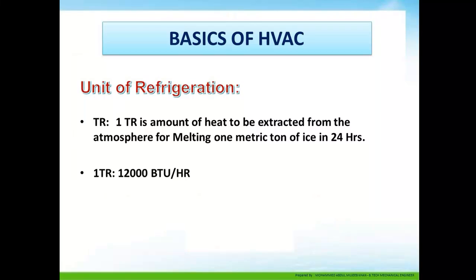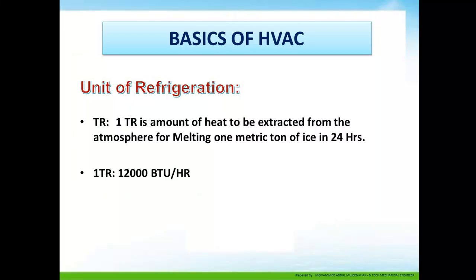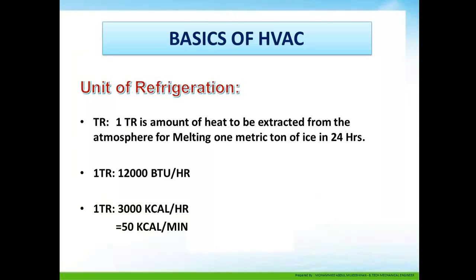Unit of refrigeration: 1 TR (ton of refrigeration) is the amount of heat to be extracted from the atmosphere for melting 1 metric ton of ice in 24 hours. 1 TR is also equal to 12,000 BTU per hour, 3,000 kilocalories per hour, or 50 kilocalories per minute.